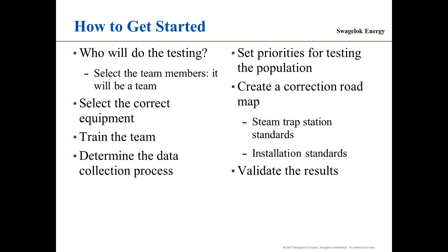Create a correction roadmap. Okay, don't get started unless you have a steam trap station standard. Okay, so what does that mean? If you go out and find a steam trap station or a steam trap to replace, what are you going to replace it with? A percentage of your steam trap failures is because of misapplication with the design of the steam trap. You know, installation standards. You've got to have standards. I mean, that's the beginning of the program. And then the next thing, validate your results.